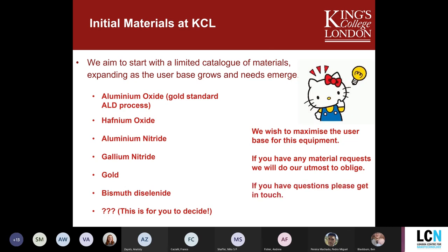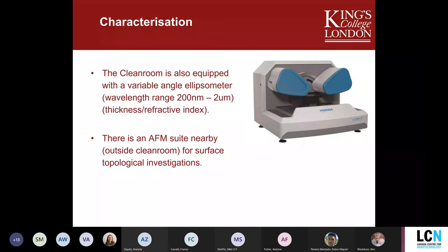As part of the Strand Research Facility, we also have a variable angle ellipsometer available, working in a wavelength range from 200 nanometers to approximately 2 micrometres. This allows you to obtain thickness and refractive index from films deposited using PALD, check for inhomogeneities, and check uniformity across a wafer. You can also extract the refractive index to get hints about impurities. This can be used before and after deposition. There is also an AFM suite nearby for surface topological investigations of your substrates before and after deposition.